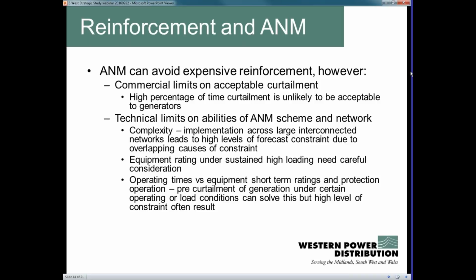That protection operates in very quick timescales, whereas active network management operates in probably tens of seconds or minutes. So if we're trying to reconfigure a network where we have very short-term high overloads, there's a risk the protection will operate before the active network management. We have to be careful about the design to avoid that.